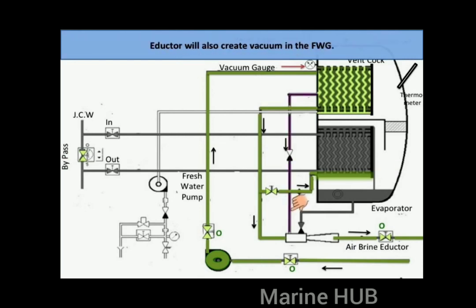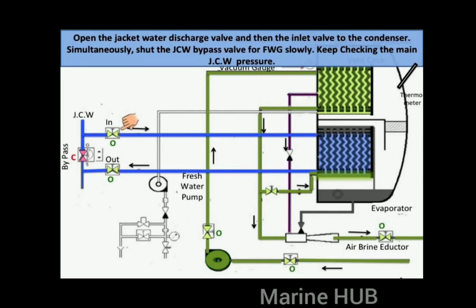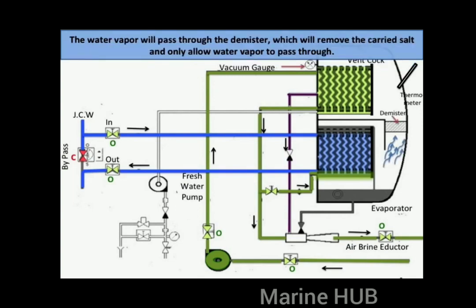The eductor will create the necessary vacuum in the fresh water generator. Open the jacket water discharge valve and then the inlet valve to the condenser. Simultaneously shut the jacket water bypass valve for the generator, while slowly checking the main jacket water pressure. Water vapor will be created by heating from the jacket water temperature, as at low pressure water boils at lower than the normal boiling temperature. The generated water vapor will pass through the demister.